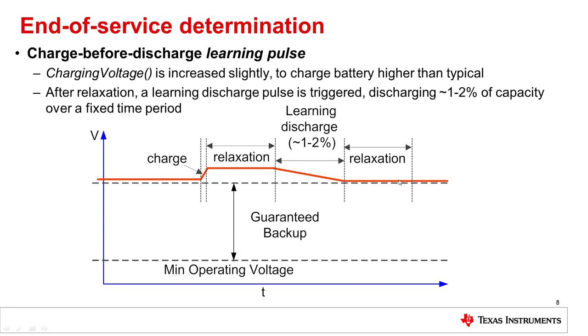The gauge itself captures all the voltage, current, and temperature throughout this entire operation and uses this in the calculations. You can see that this does not affect your guaranteed backup at all, because normally if you're only charging up to 4.0V, we're actually overcharging slightly — still within allowed limits — and using the discharge from that overcharge back down to a level closer to what you normally have as full charge. So you're not impacting the guaranteed backup capacity available to the system at all in this approach.